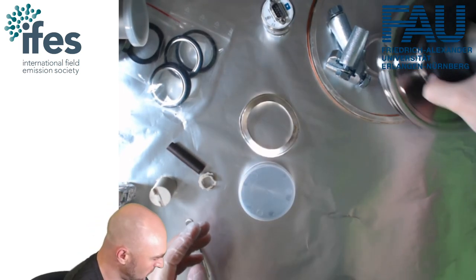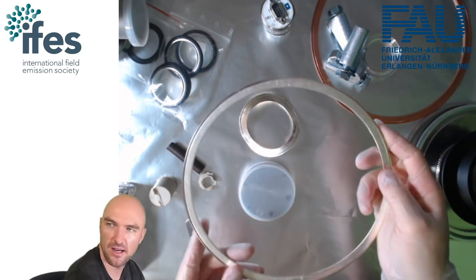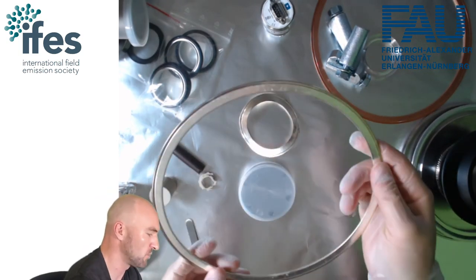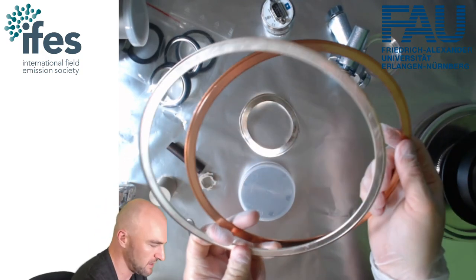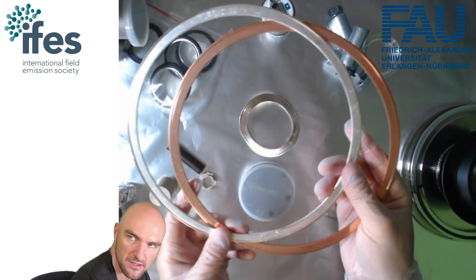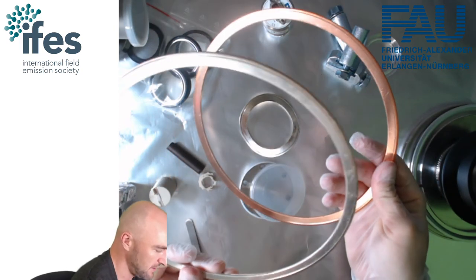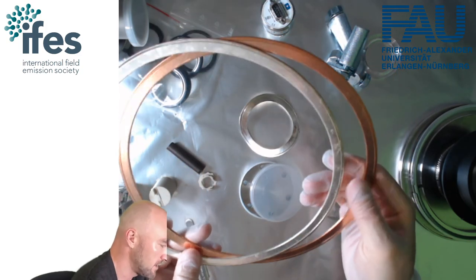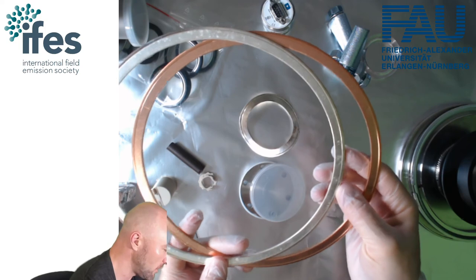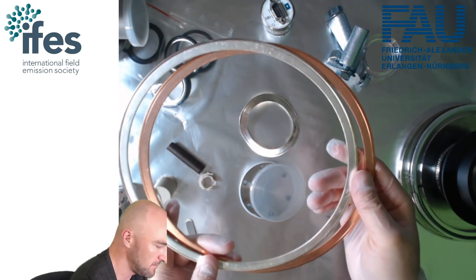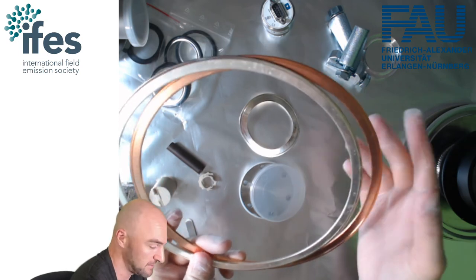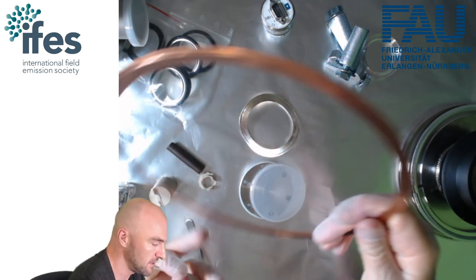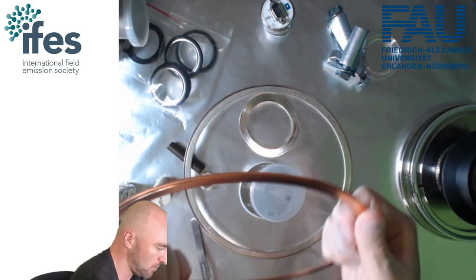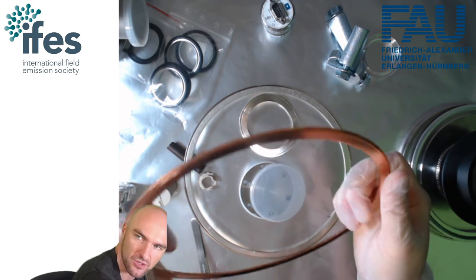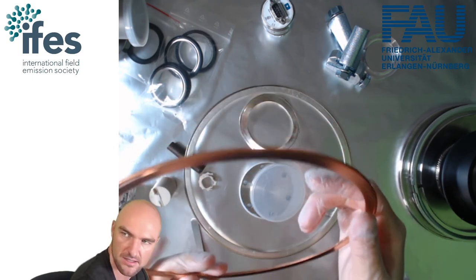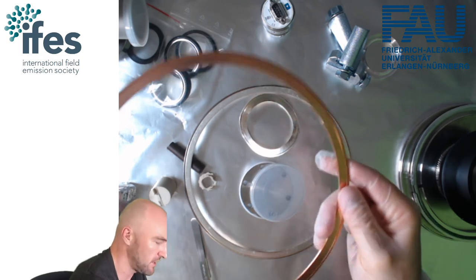And in between, we actually put seals like this. So this here would be a CF200 seal, and this would also be a CF200 seal. The difference between the two seals is that the silverish seal is silver plated, and the copper colored seal is just copper. And essentially you get three different types of those seals, four different types if you count all combinations, and you can get seals that are rolled copper, so the copper is relatively strong, and this would be one of those. Yeah, so this is relatively strong copper because it's essentially cold rolled copper and just a ring punched out.